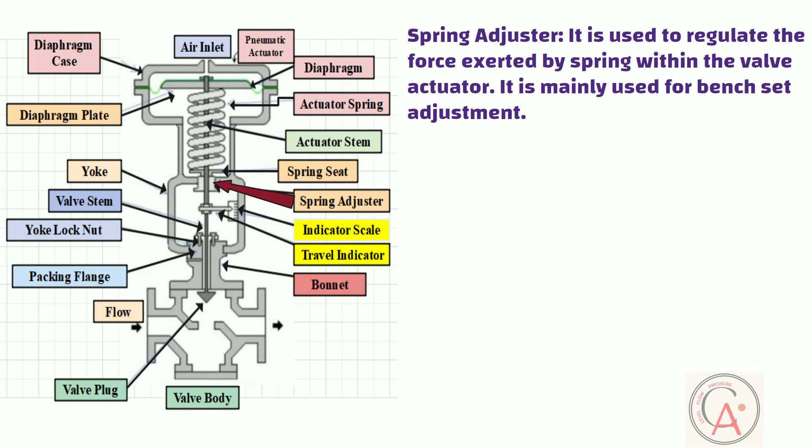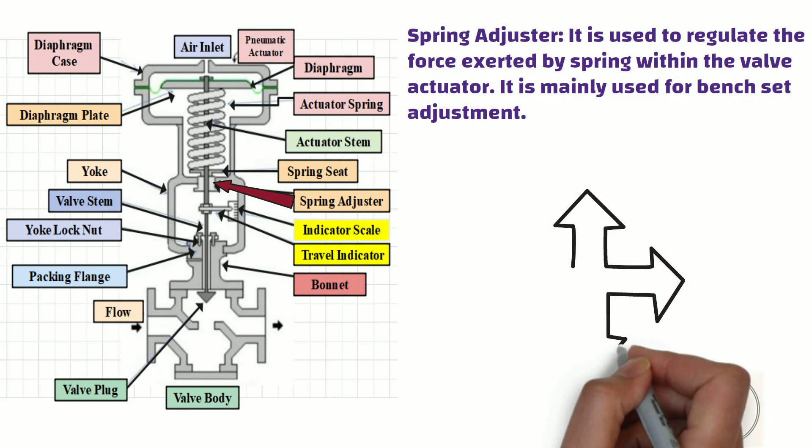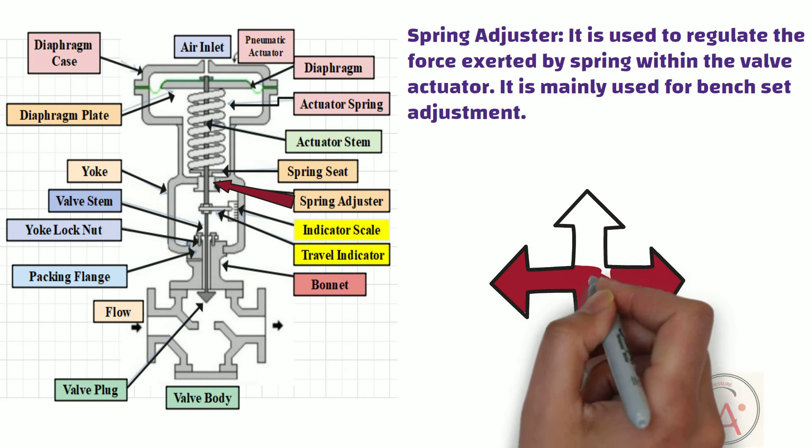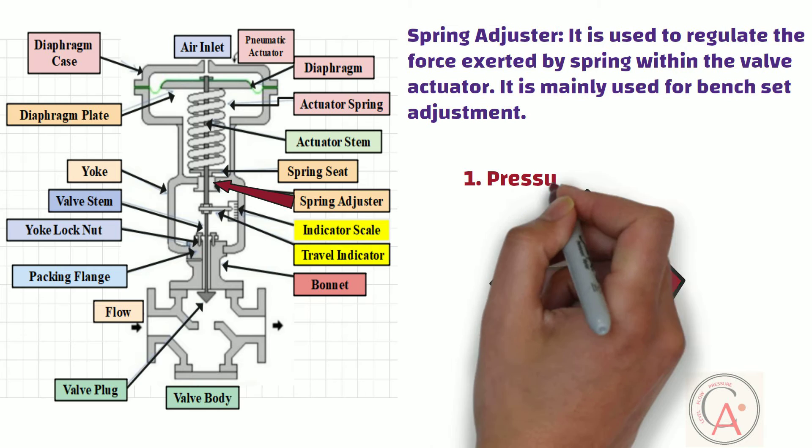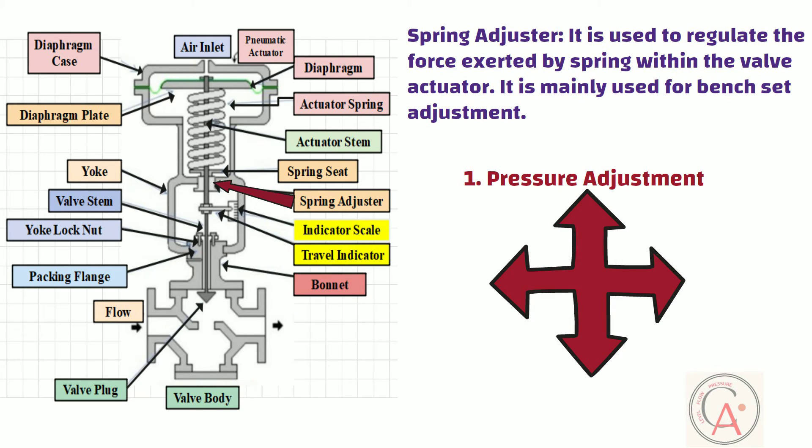By turning the spring adjuster, we can change the actuator response. There are mainly four functions of the spring adjuster. First of all, it can be used for pressure adjustment. By turning the spring adjuster nut, the technician can increase or decrease the force exerted by the spring. This adjustment is essential for calibrating the valve to specific operating conditions such as different flow rates or pressure levels.